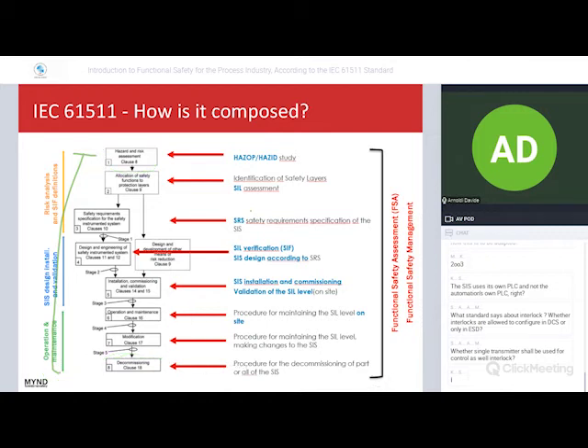We can define three different zones of the life cycle. The first zone is the risk analysis and the safety instrumented function definitions. The second zone is the safety instrumented system design, installation, and validation. The third is the operation and maintenance of the SIS. The life cycle is related only to the SIS, not to the process plant. And then we have all the steps to follow in order to comply with the standards.